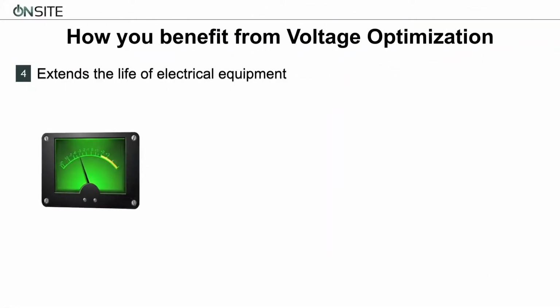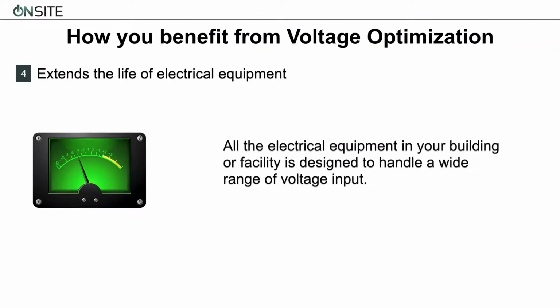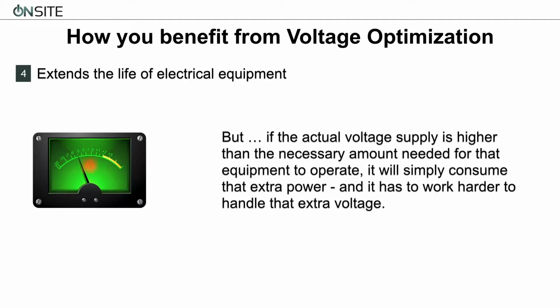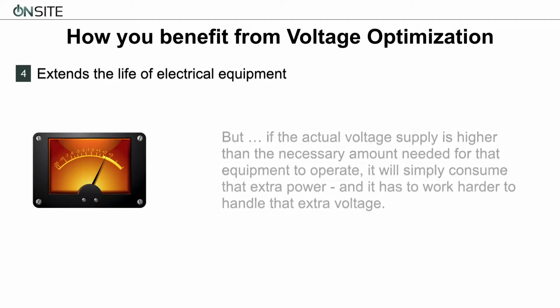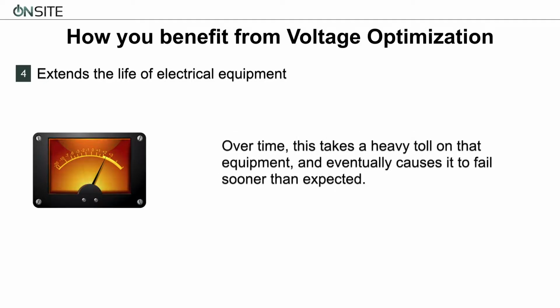Voltage optimization also extends the life of electrical equipment. All of the electrical equipment in your building or facility is designed to handle a wide range of voltage input. But if the actual voltage supply is higher than the necessary amount needed for that equipment to operate, the equipment will try to consume it, which requires the equipment to work harder to handle all that extra voltage, causing overheating. Over time, this takes a heavy toll on your equipment and eventually leads it to failing sooner than expected.